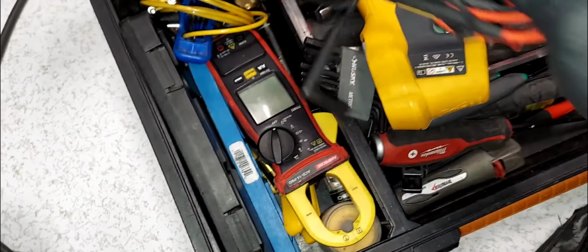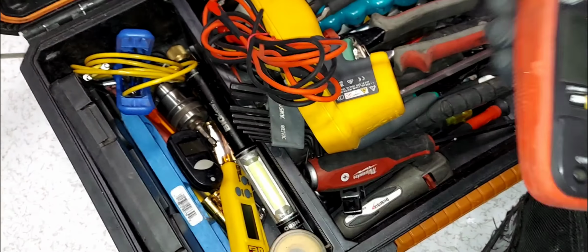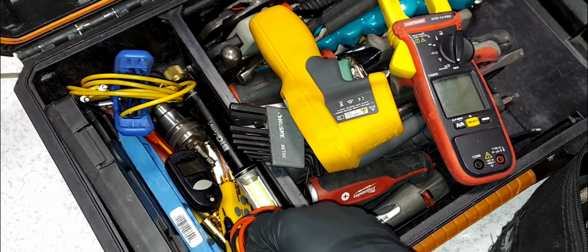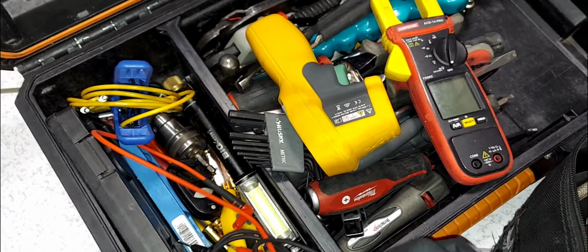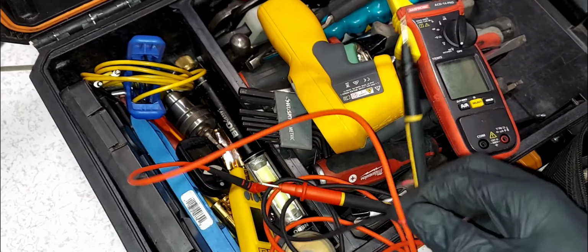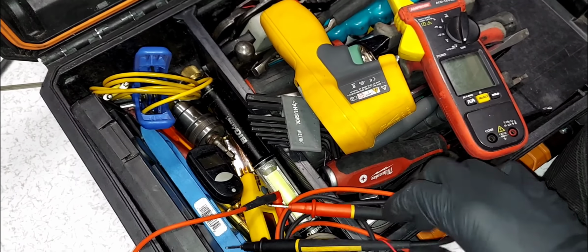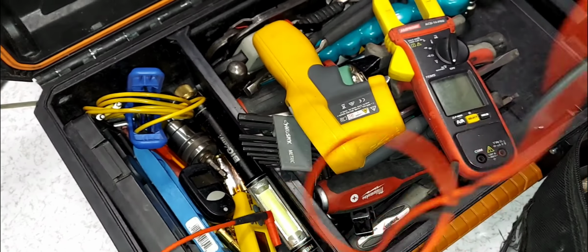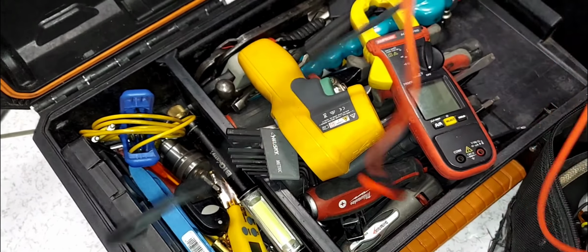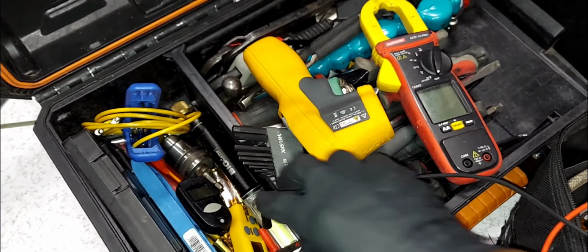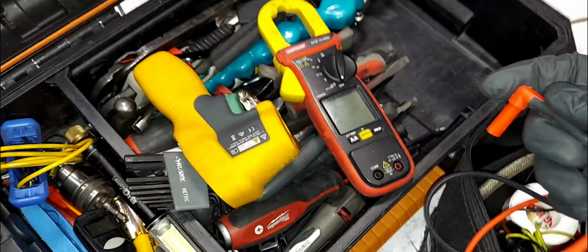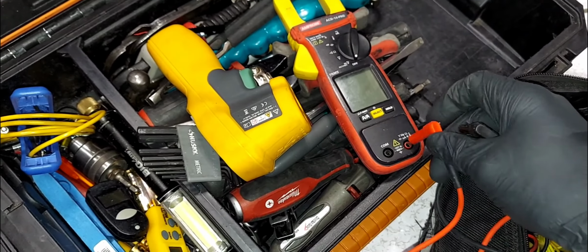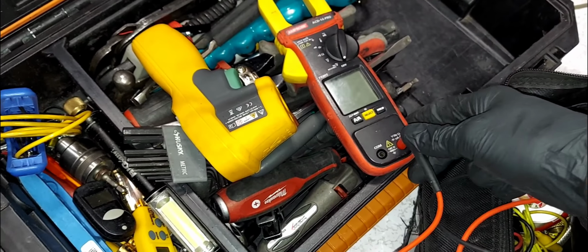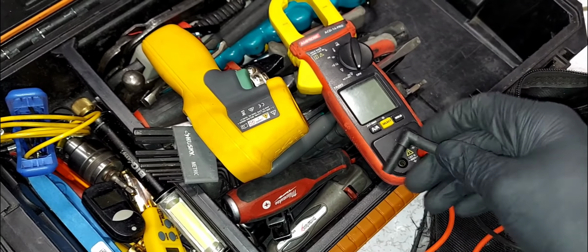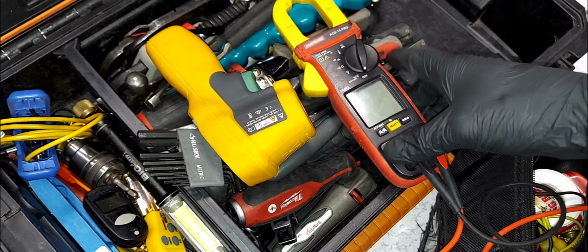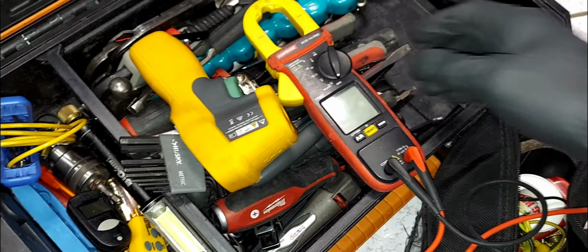So I'm just gonna grab my meter and do some testing on the motor winding. Make sure the motor windings are not shorted to ground and they are not open. I'm gonna check my power supply coming into the main fan contactor, make sure that my fuses are good and that my power supply is good, because all this could lead to the overload being tripped. And just to verify, I'm almost positive that I'm going to find that those contacts and the overloads are open.